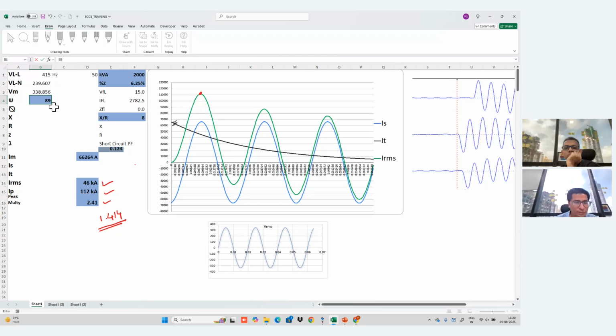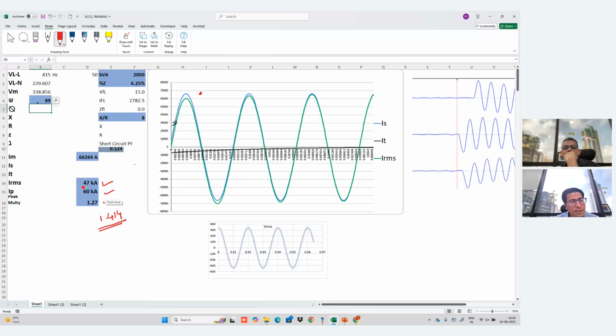Now this is 46, this is 46, this is 112. I'm changing this to 89, and you can see this remains 47, but the 112 has changed to 60 kiloampere. Now the peak, you can see it's changed to 60 kiloampere when the fault occurs at the peak of the voltage point on the wave. Okay, so this is the first case.